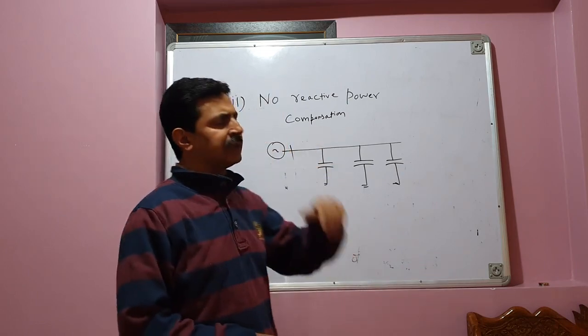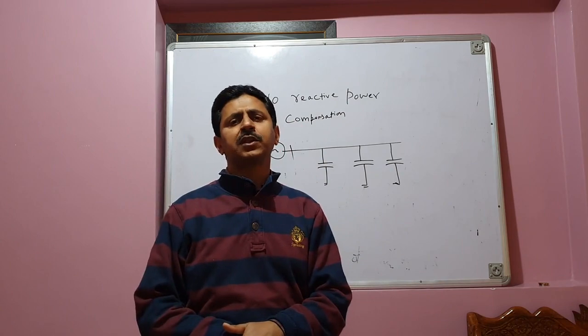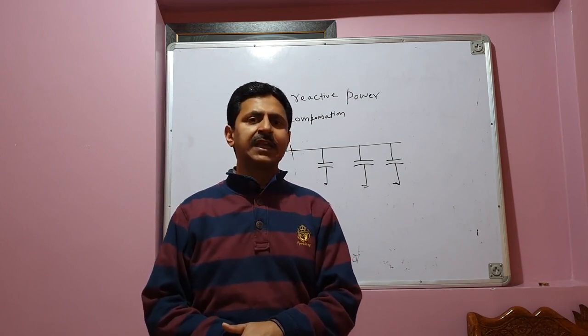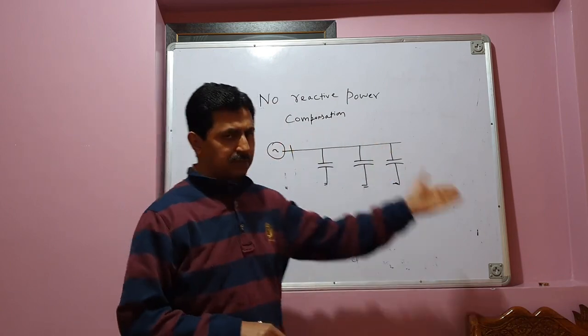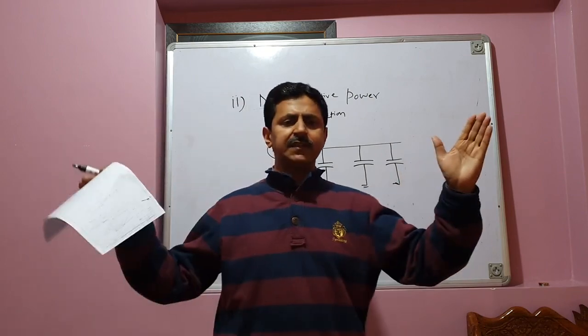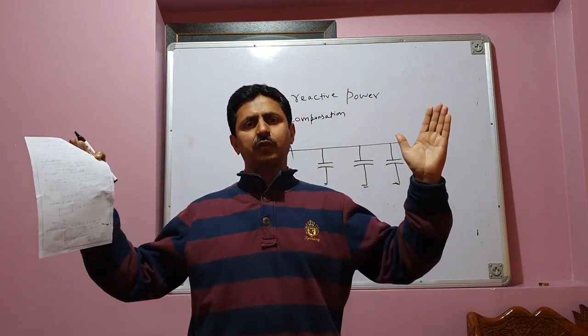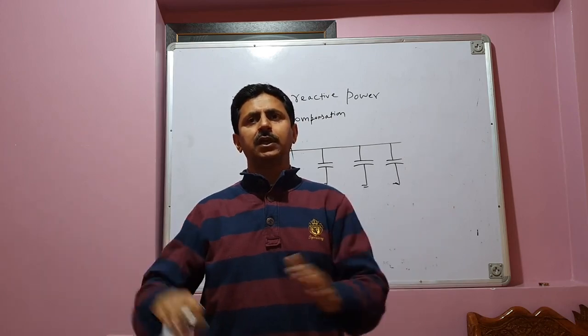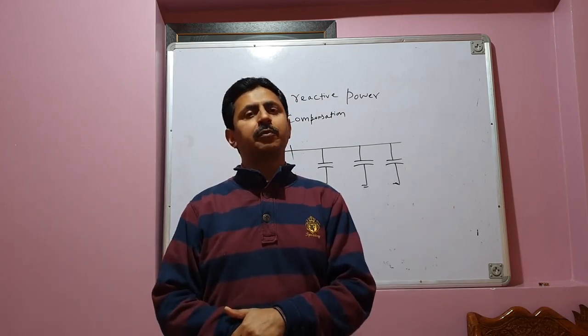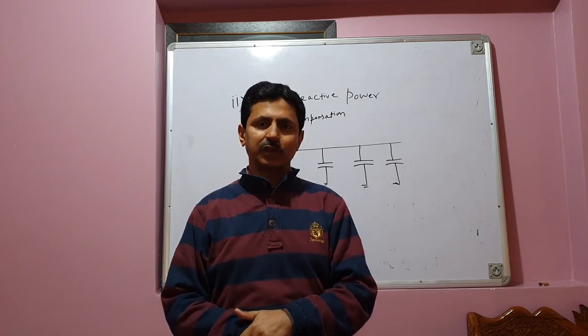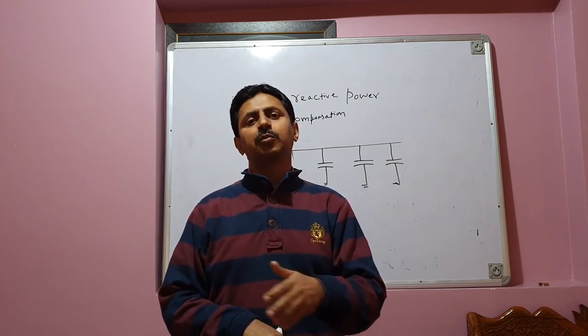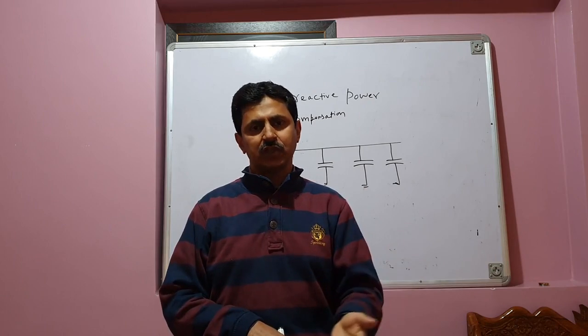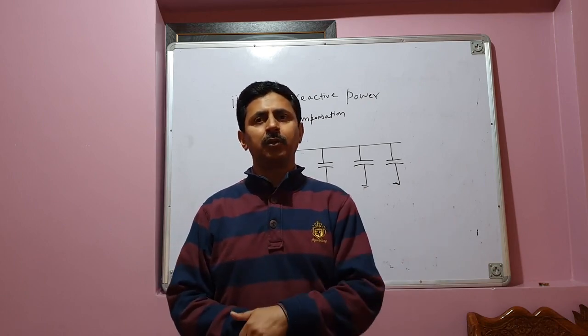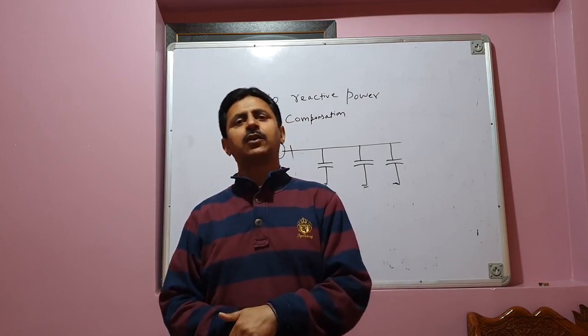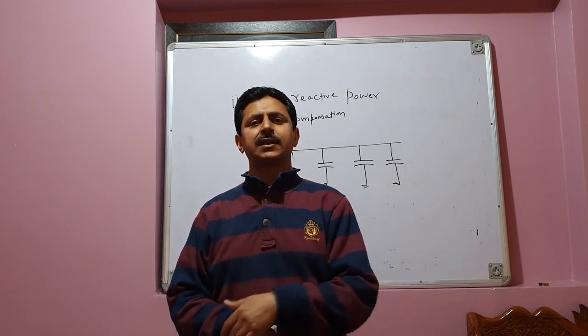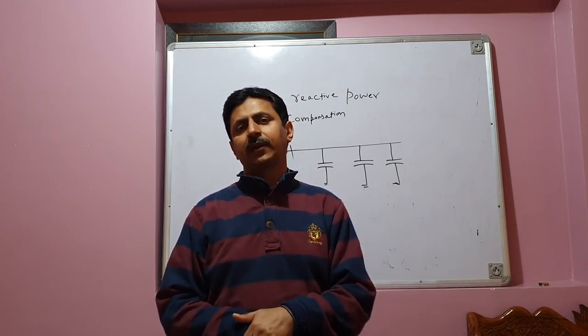We don't need this compensation if we are transmitting the power over a DC line rather than an AC line, because in DC there is no concept of reactive power. You have a DC transmission line, DC power is flowing over it, only active power is flowing over it. There is no reactive power concept in a DC transmission line. So therefore you don't need the reactive power compensation, shunt compensation. You don't need to connect a STATCOM, you don't need to connect an SVC, you don't need to connect a thyristor controlled series capacitor and all that for reactive power compensation.